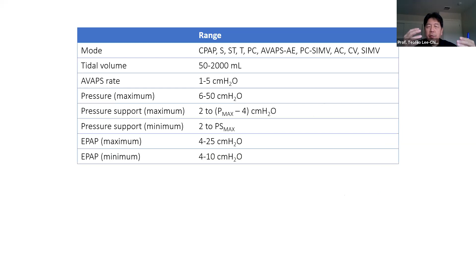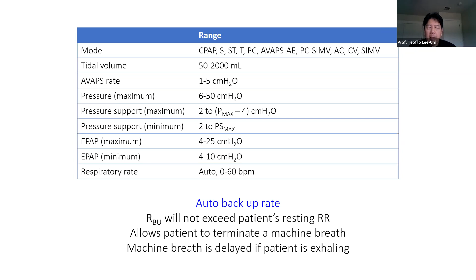Respiratory rate can either be manually entered between 0 to 60 breaths per minute or automatic. And I would like you to consider perhaps using an automatic backup rate because of its multiple benefits. One, the backup rate will not exceed the patient's resting respiratory rate. Secondly, it might improve ventilator patient synchrony. It would allow the patient to terminate a machine breath if they decide to breathe out, and it allows the patients to also exhale by enabling the machine to delay its delivered breath.